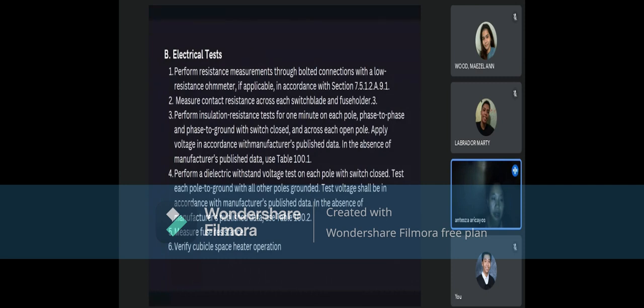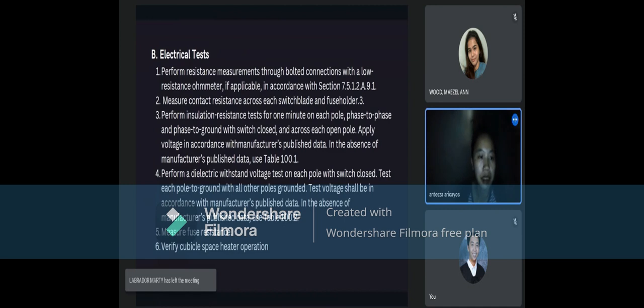In electrical test of 7.5.1.2, the first is perform resistance measurements through bolted connections with a low resistance ohmmeter, if applicable, in accordance with section 7.5.1.2.A.9.1. The second is measure contact resistance across switch blade and fuse holder. And the third is perform insulation resistance test for 1 minute on each pole, phase to phase and phase to ground, with switch closed and across each open pole. Apply voltage in accordance with manufacturer's published data, using table 100.1.